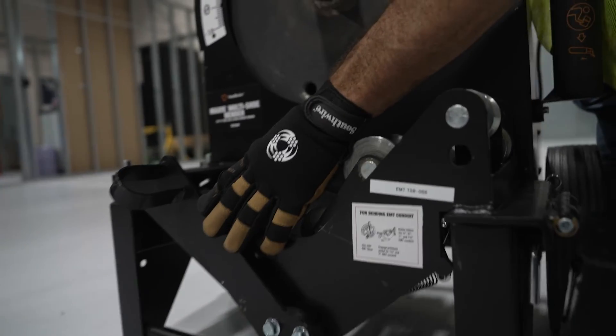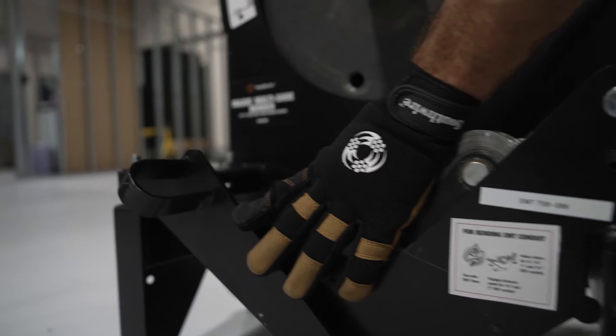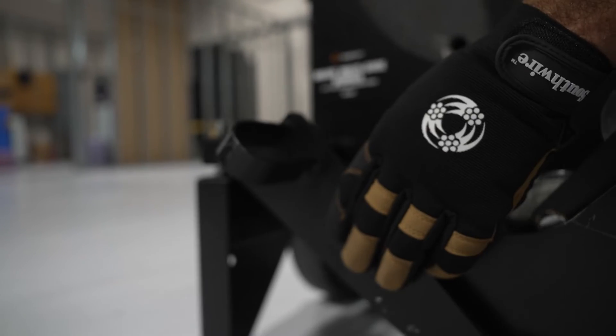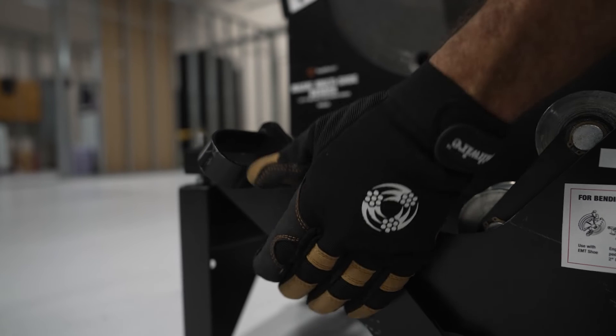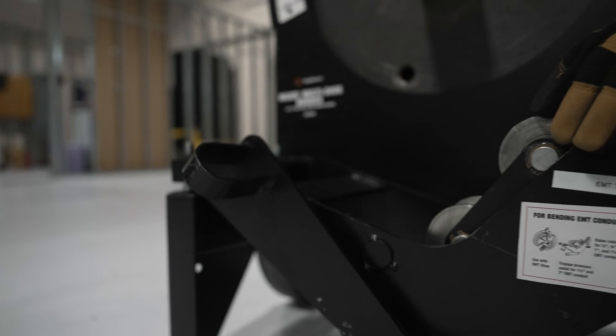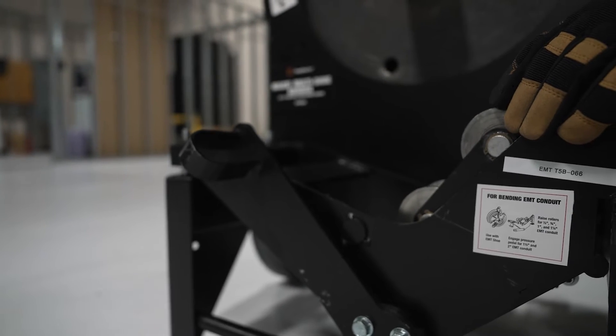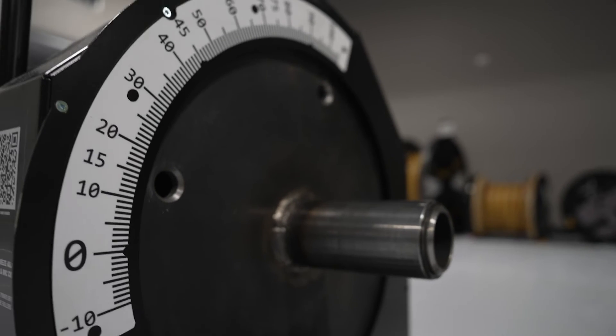The roller assembly has pressure rollers and a pressure pedal which must be used when you're bending inch and a half and two-inch EMT conduit. If you're not bending inch and a half or two-inch EMT conduit, the pressure pedal is not used. Let's install the bending shoe.